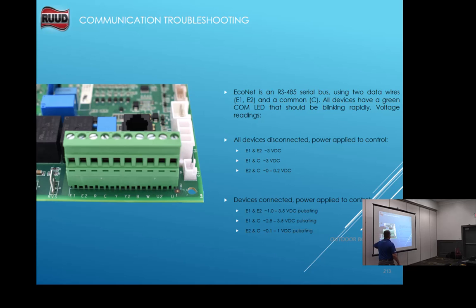I tell you this because last year I drove to Tennessee with a communication error. I've done it twice. Contractor said, we checked all of that. We done that. I get there, I pull the controller off of the wall. I looked, I couldn't see bare wire on the common wire going behind, into the little hole into the base plate. I took my screwdriver, pushed it in, pulled that white wire out. Do you think the insulation was stripped back all the way? Nope. Took my knife, stripped the wire back, pushed it in there, pushed the controller back on the wall. Communication alarm went away. I drove 7 hours for that.